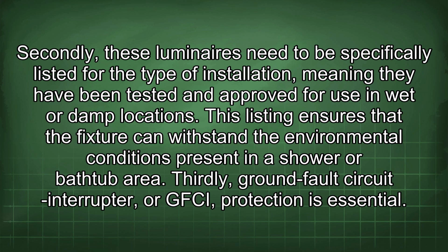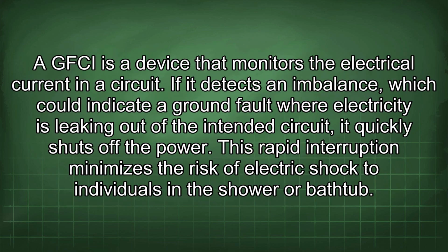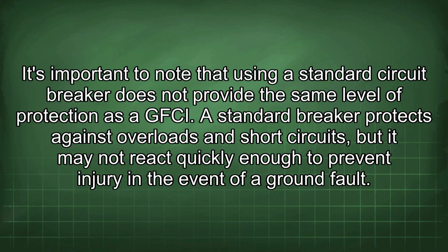Thirdly, ground fault circuit interrupter, or GFCI, protection is essential. A GFCI is a device that monitors the electrical current in a circuit. If it detects an imbalance, which could indicate a ground fault where electricity is leaking out of the intended circuit, it quickly shuts off the power. This rapid interruption minimizes the risk of electric shock to individuals in the shower or bathtub. It's important to note that using a standard circuit breaker does not provide the same level of protection as a GFCI. A standard breaker protects against overloads and short circuits, but it may not react quickly enough to prevent injury in the event of a ground fault.